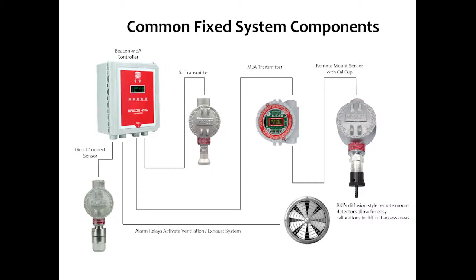Another good question is this. If the LEL gas is up in the ceiling and that's where I want to measure, every time I have to calibrate it, do I have to get a lift to go up there and do it? Yeah, pretty much. Unless you take the small step of adding a remote calibration adapter to it, and then you would drop poly tubing down to the floor, and guess what? Now you don't have to get a ladder out or a lift. There are all sorts of ways to skin the cat, and these are what the professionals are going to do when they come out and visit you.